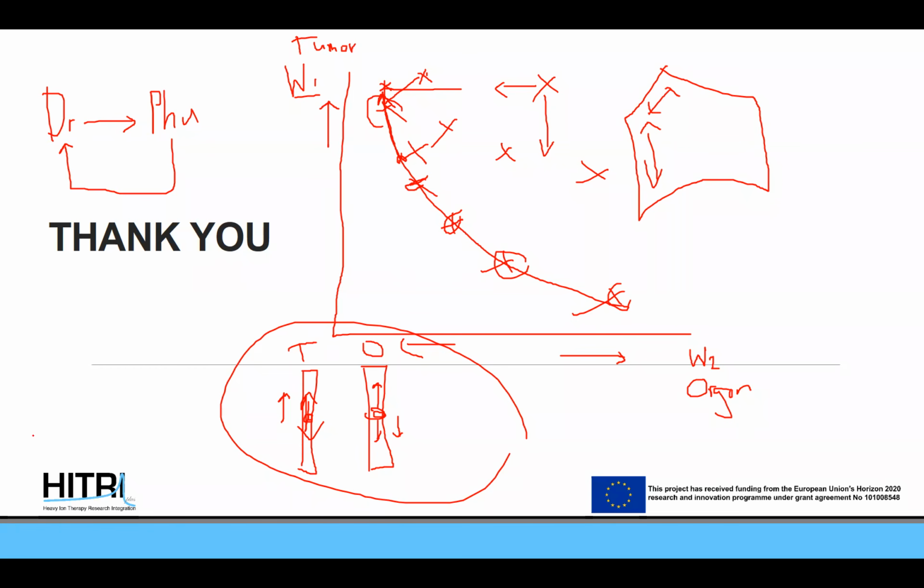So the motion is never periodic. It has a sine to the fourth power distribution that looks something like this. Because it spends most of the time in this region, which is the exhale, you gate your treatment to this region. When you breathe, the most reproducible part of your breathing is your exhale. It's long and always ends up at the end. So you target the exhale phase when you treat for motion, but it's possible.